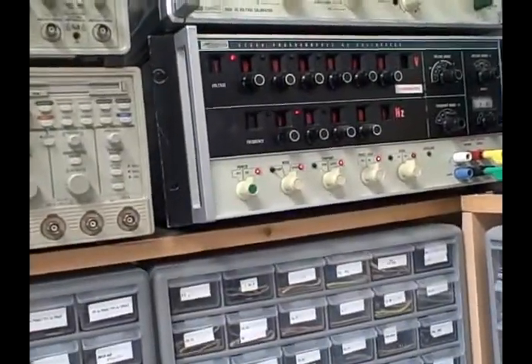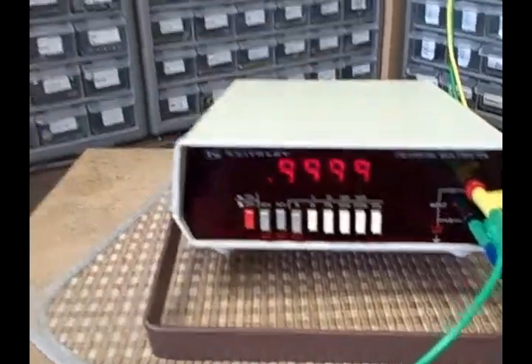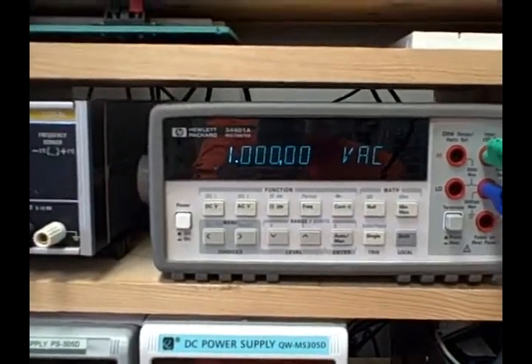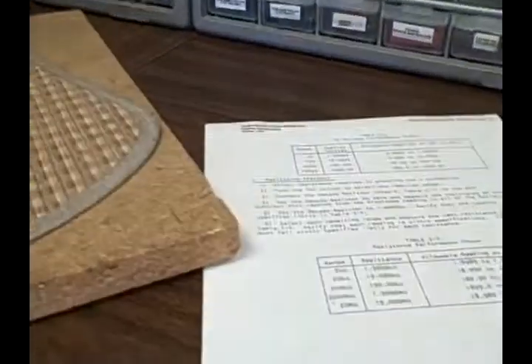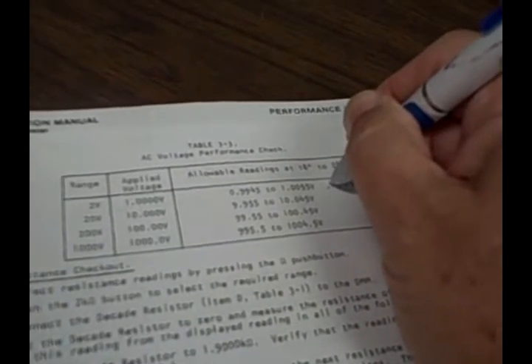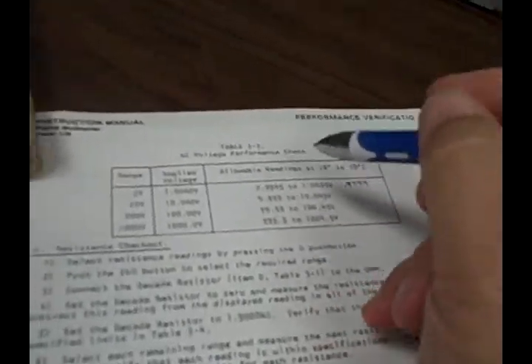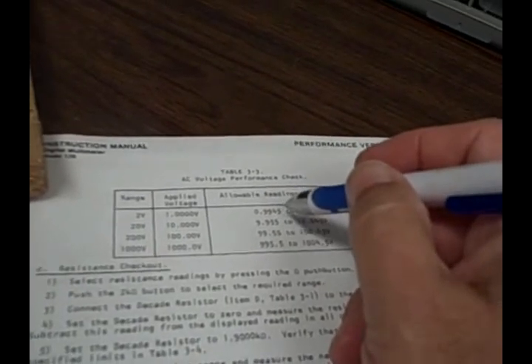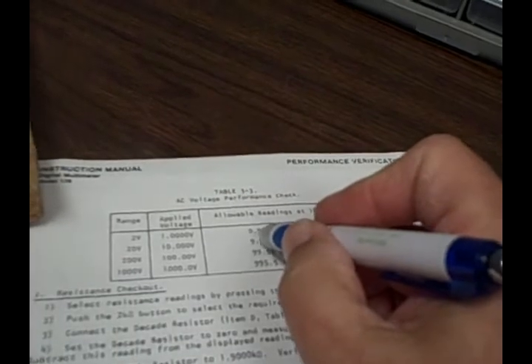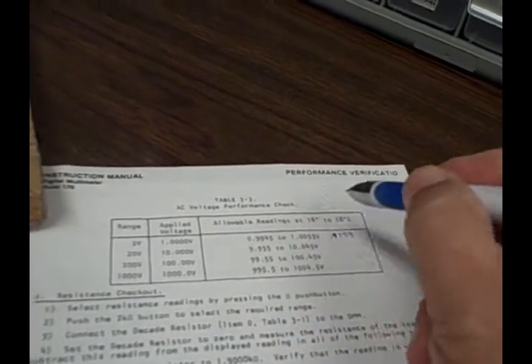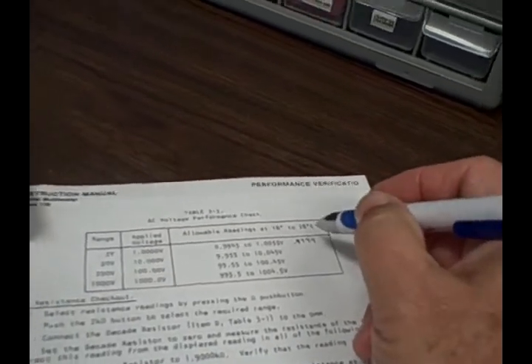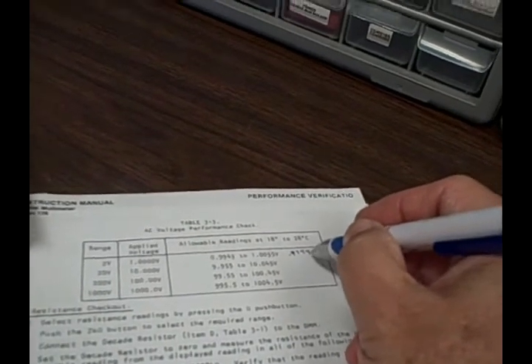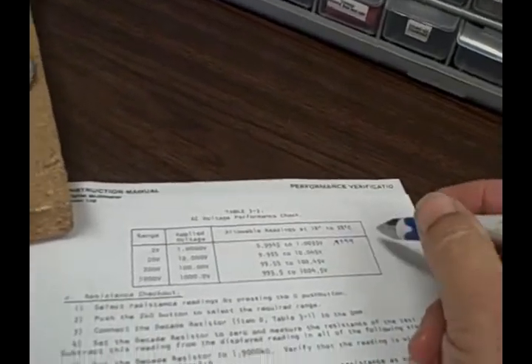Okay, we're getting our AC voltage now from this Fluke 5200A. We're on the AC range, and we are reading right now 1.00 volts AC on the HP. And we see that we're reading all 9s on the Keithley. 0.9999 with a 1 volt input. Basic accuracy for the AC ranges is about 0.3% plus so many digits. We would be good if we read between 0.9945 volts to 1.0055 volts. We're right smack dab in the middle at 0.9999, 100 microvolts off of a perfect 1 volt. So beautiful there. Let's move to the 20 volt range.